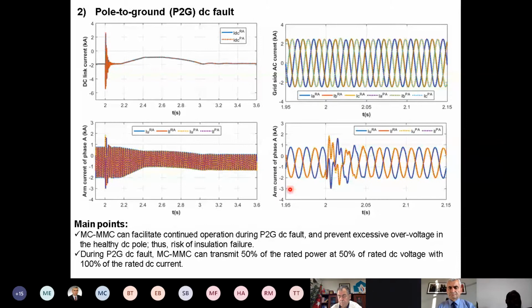And also in summary, we can say the mixed cell MMC can continue to operate during a pole to ground DC fault and prevent excessive overvoltage in the healthy DC pole. Thus, the risk of cable failure is reduced. And during a pole to ground DC fault, the mixed cell MMC can transmit 50% of the rated power at 50% of DC voltage with 100% of the rated current.